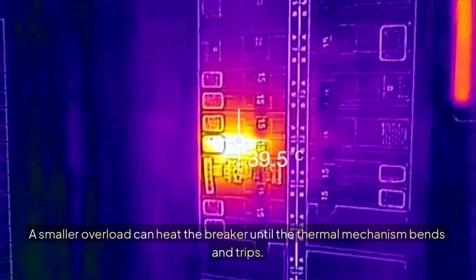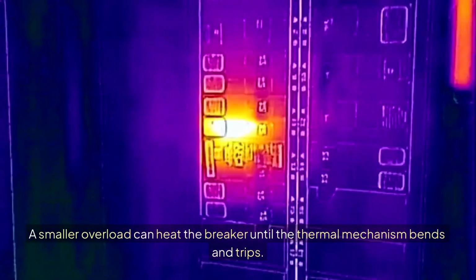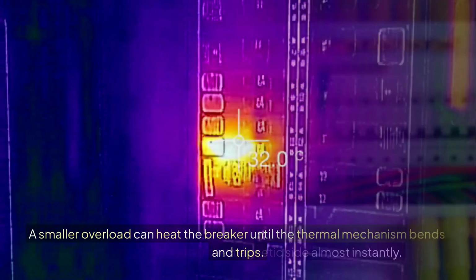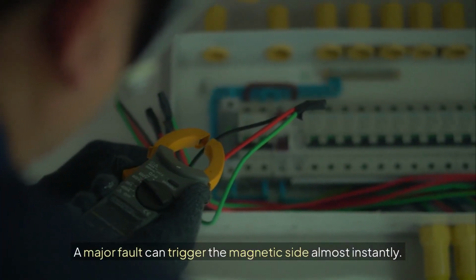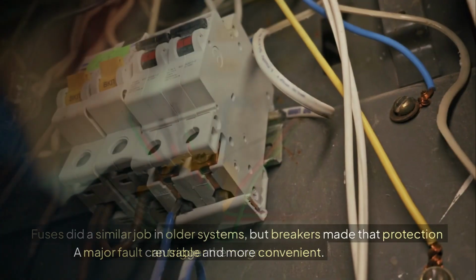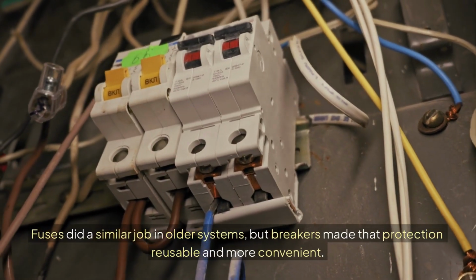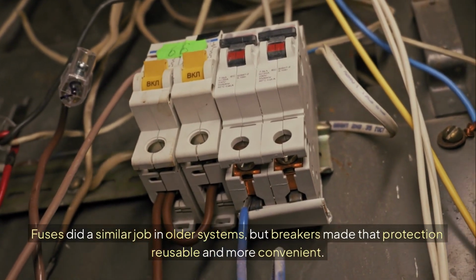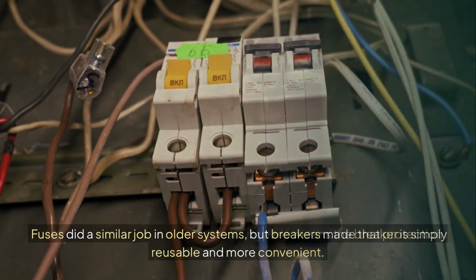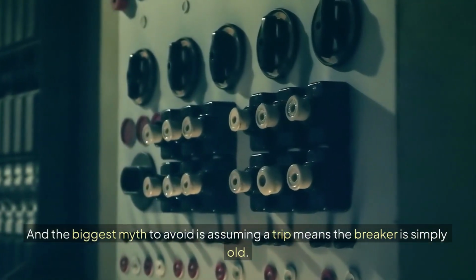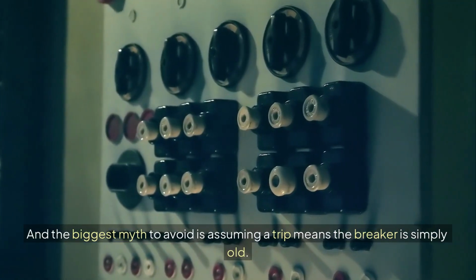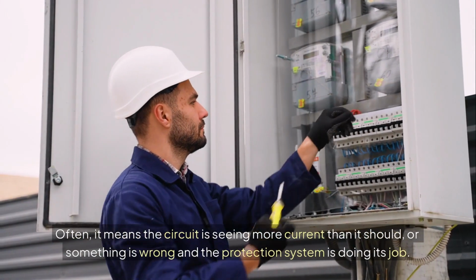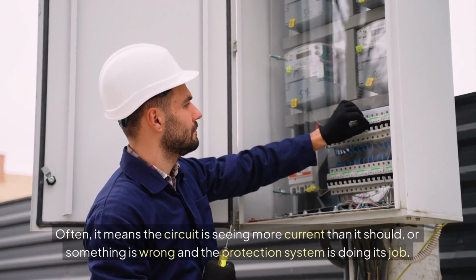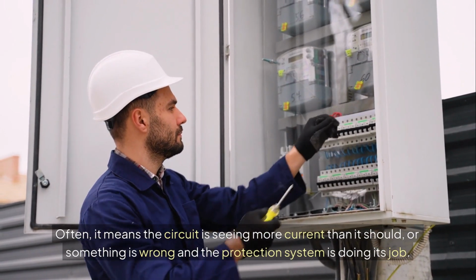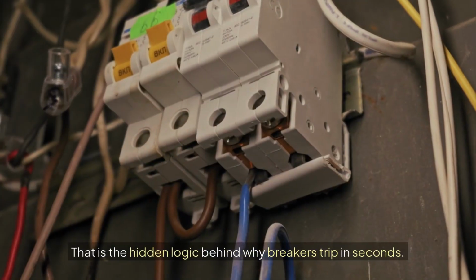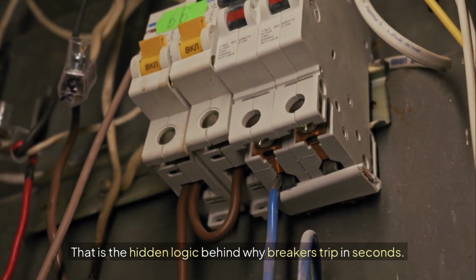A smaller overload can heat the breaker until the thermal mechanism bends and trips. A major fault can trigger the magnetic side almost instantly. Fuses did a similar job in older systems, but breakers made that protection reusable and more convenient. And the biggest myth to avoid is assuming a trip means the breaker is simply old. Often, it means the circuit is seeing more current than it should, or something is wrong and the protection system is doing its job. That is the hidden logic behind why breakers trip in seconds.